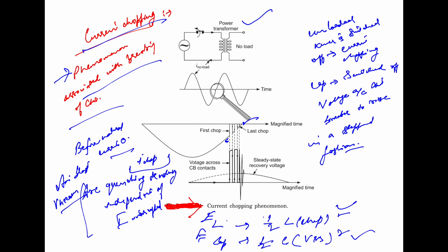Now, the system capacitance is quite low. It is the stray capacitance, as we have discussed already. So the small value capacitance, this C, needs to be charged to a very high voltage, which is designated as V res, and which is also known as the restriking voltage.